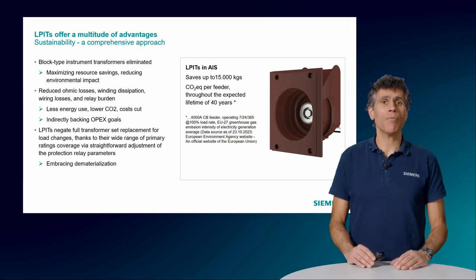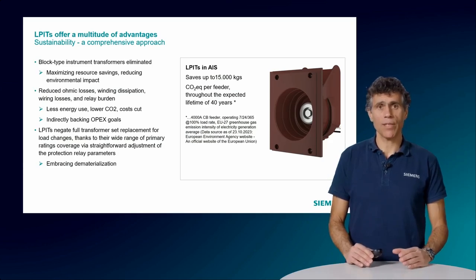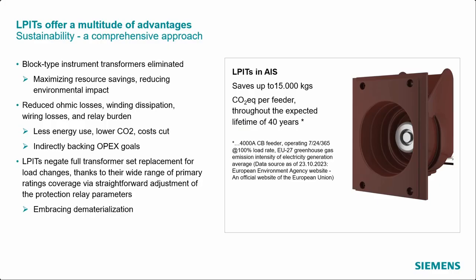However, a special property of LPIT technology is the low output power and the small secondary voltage of the sensor. This ranges from millivolts to a few volts. Thus, the danger for executing personnel is significantly lower compared to the conventional transformers. These involve many cables and terminals and are inherently prone to human error. In LPITs, a single cable plugged in the relay directly from the LPITs reduces human interaction and certainly leads to a decreased risk of malfunction.